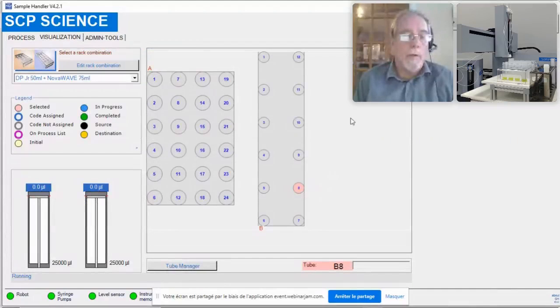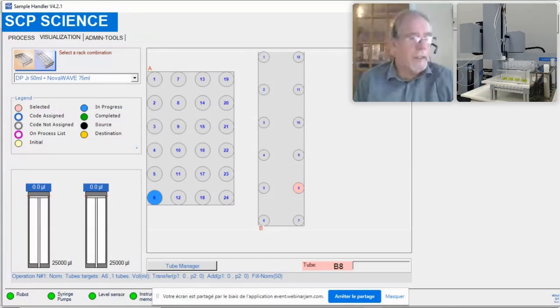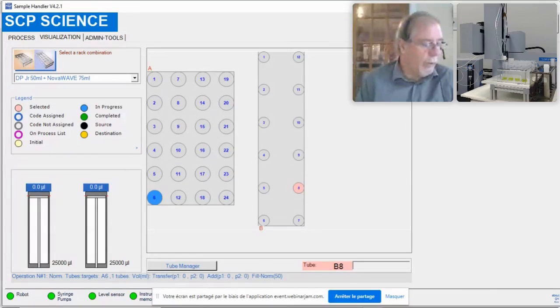AccuNorm. And the theory of using AccuNorm is that it's an unknown volume. So if you put 8 mils of acid into a vessel and did a digestion, we don't know how much has left with precision. But AccuNorm will measure the volume in the tube and then do the calculation to add the remaining solution up to your volume that you would like to normalize. Now you can use any normalization volume that you want. It doesn't matter how much the liquid level is in the tube, it will do the calculation.